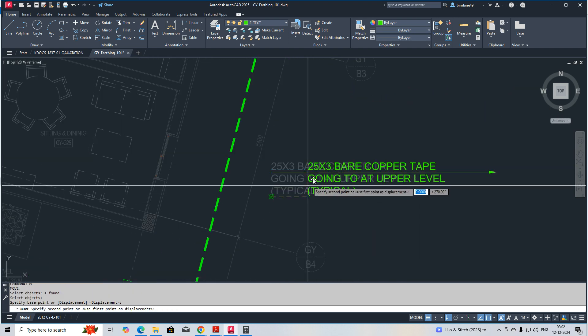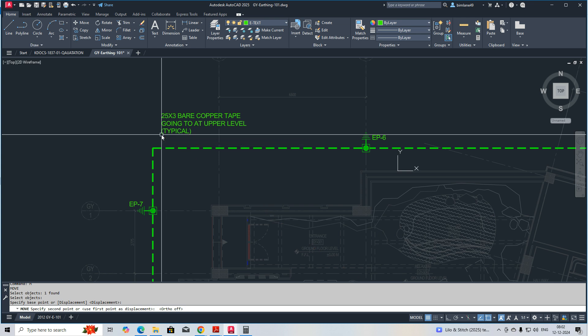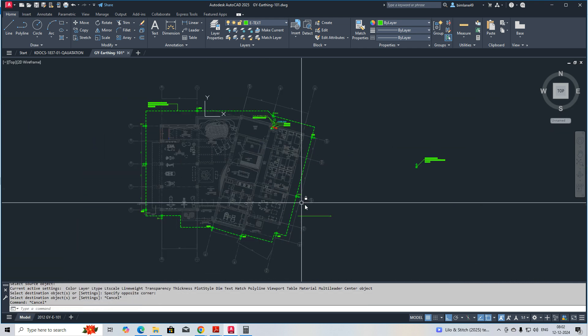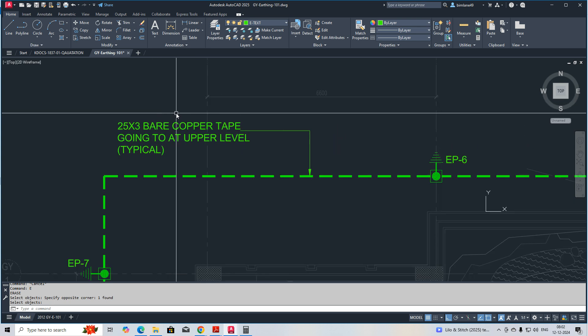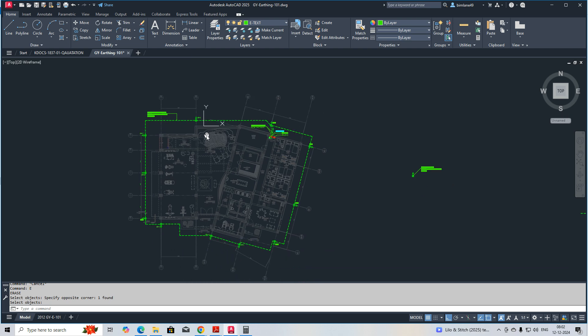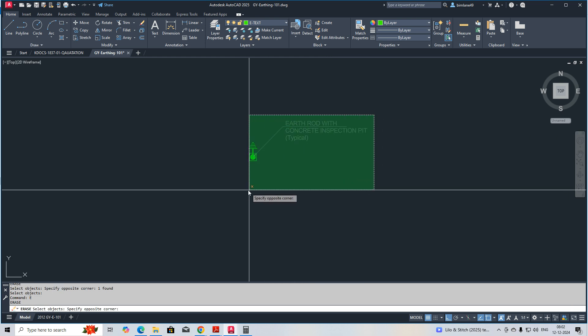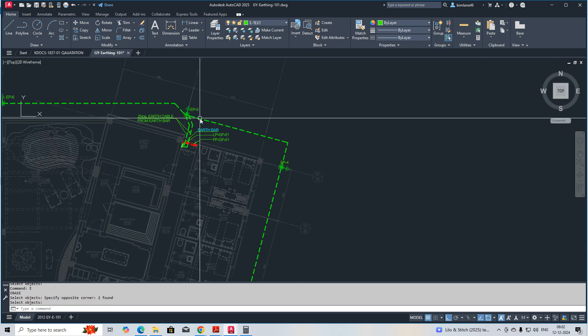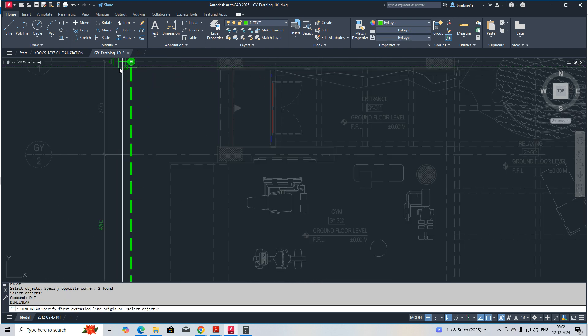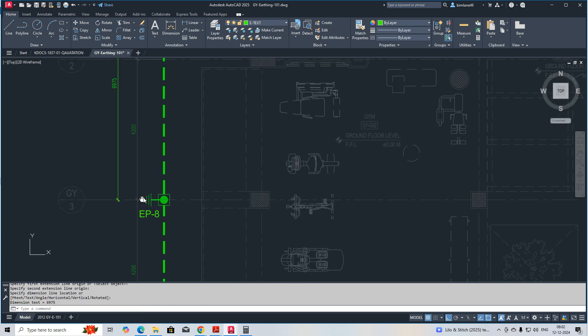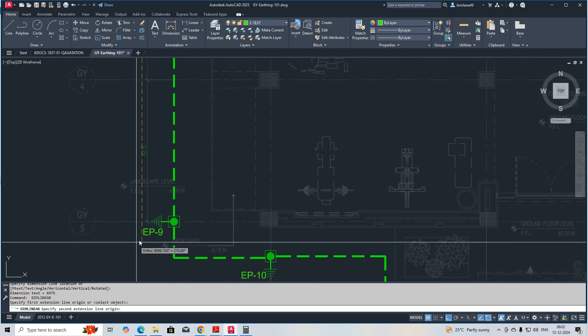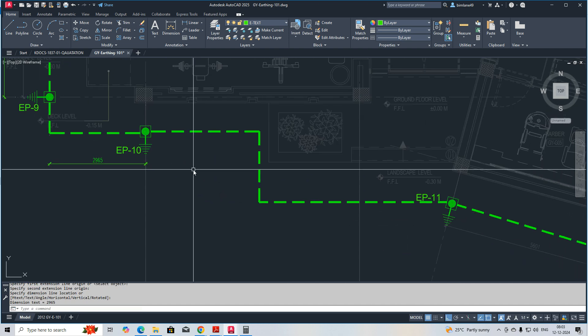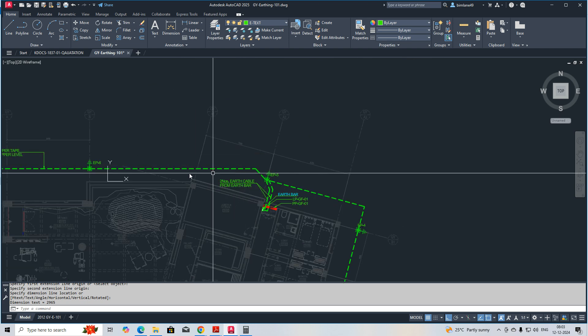You can give a typical note for this wherever required. Add a leader here and match it with the leader also. The note reads: '25x3 bare core bare copper tape going to upper level — this is a typical inspection pit note.' If you want to make dimensions, you can do that too. Make the distance dimensions, and for all the pits you can clearly define the dimensions.